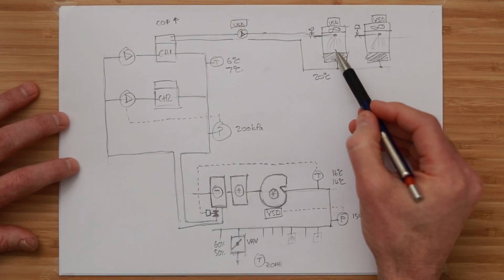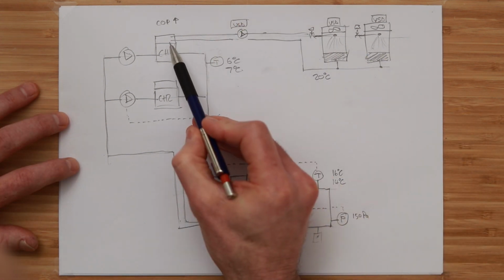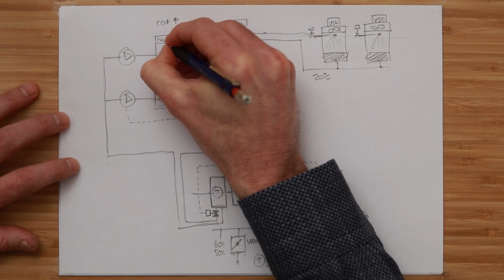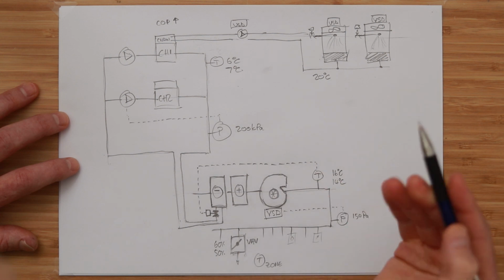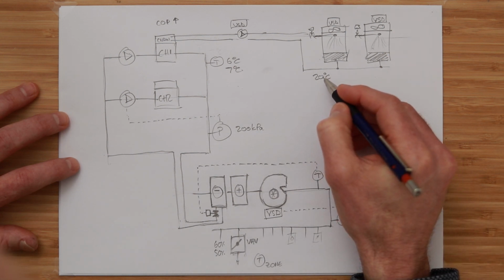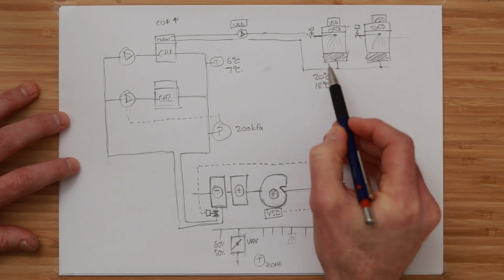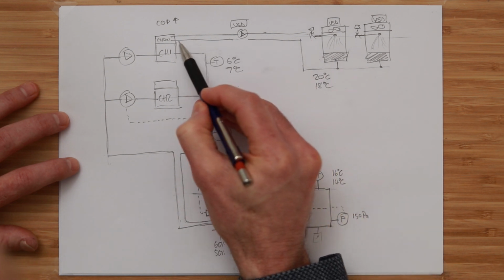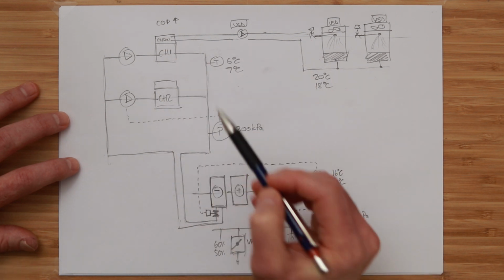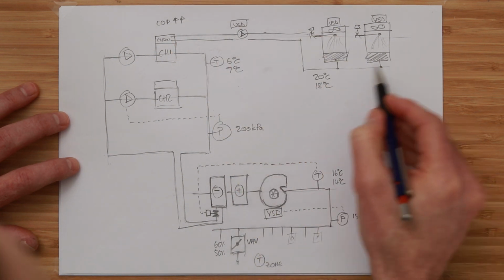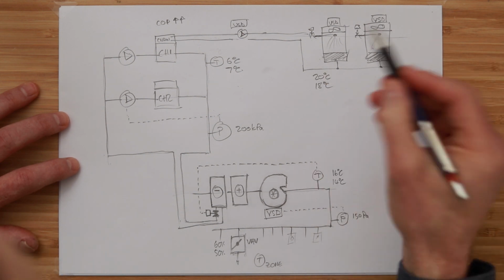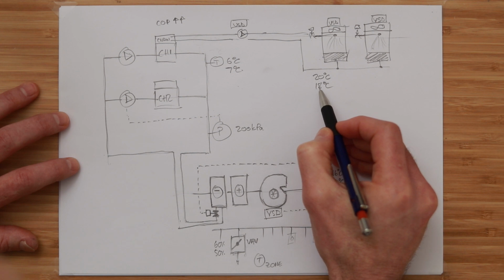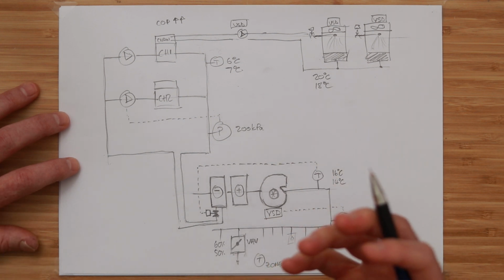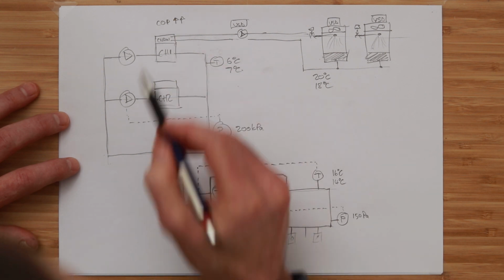So here we have two cooling towers providing heat rejection for the chiller's condenser. We already have control strategies where we actively reduce the condenser water temperature. As we reduce this condenser water temperature, that cooler water goes through the chiller's condenser, and that makes the chiller more energy efficient and the chiller's COP goes up. So as we're looking at wet bulb temperature, et cetera, we reduce the condenser water temperature automatically through an optimized control strategy, and that makes the chiller more energy efficient.